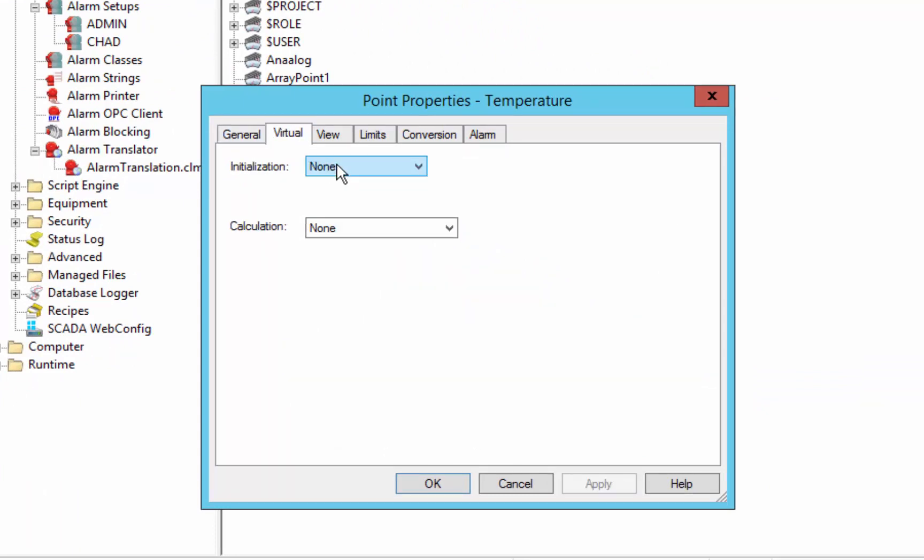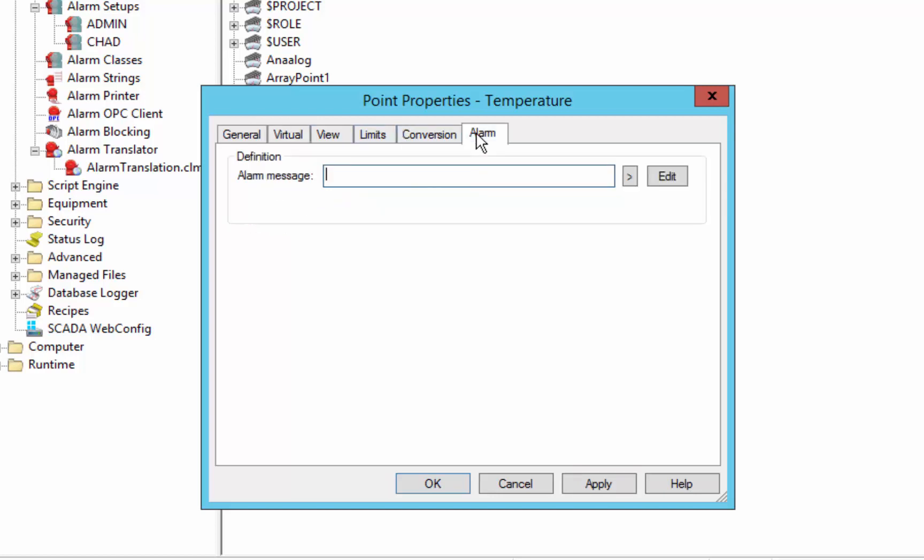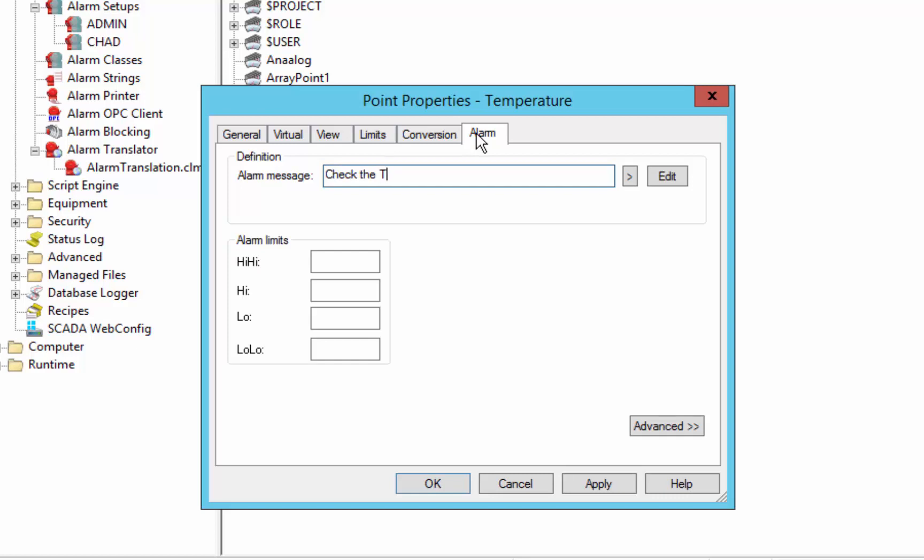We'll say that normal operating temperatures are around let's say 15 degrees. And we want to specify when we want an alarm indicating that that temperature is out of an acceptable range. So we'll give it an alarm message: Check the temperature. And this is a really simple alarm just using a level alarm, specifying what limits are in alarm.